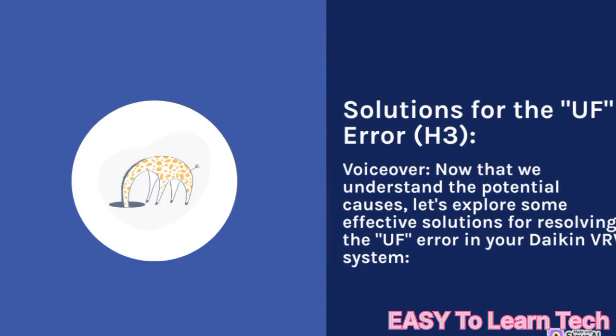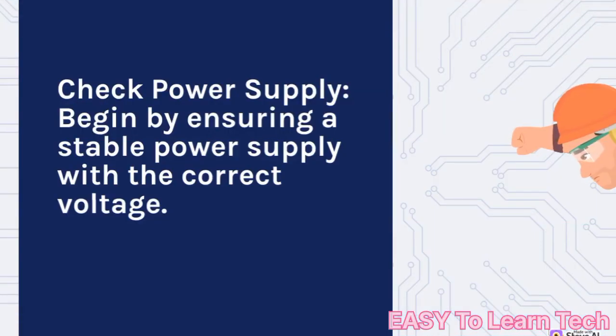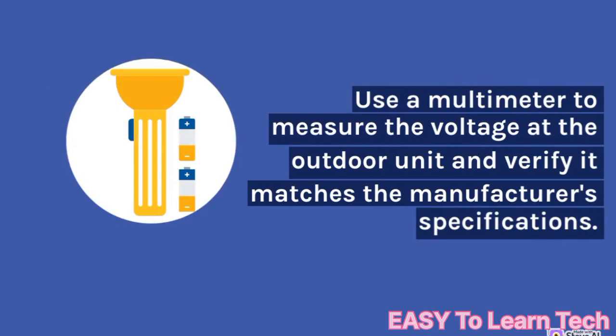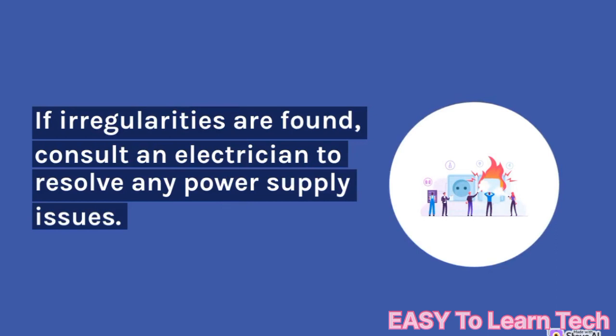Now that we understand the potential causes, let's explore some effective solutions for resolving the UF error in your Daikin VRV system. Check power supply: begin by ensuring a stable power supply with the correct voltage. Use a multimeter to measure the voltage at the outdoor unit and verify it matches the manufacturer's specifications. If irregularities are found, consult an electrician to resolve any power supply issues.